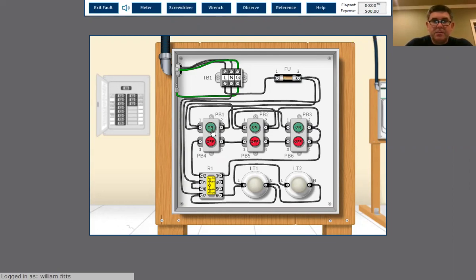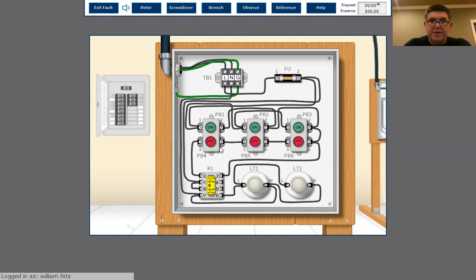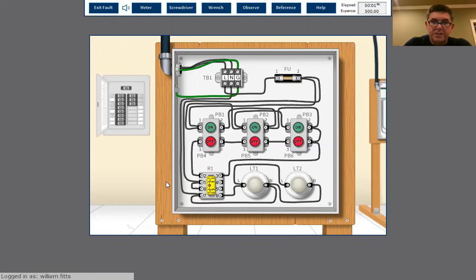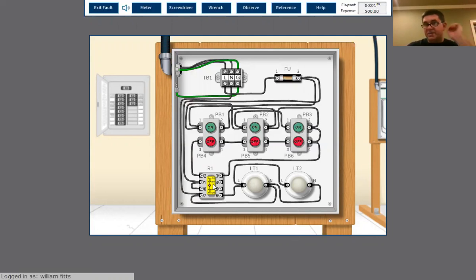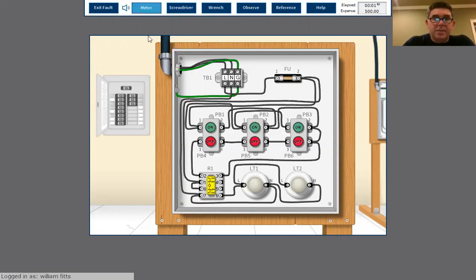There's no light, but what am I gonna look for? Right down here, see that relay? I'm gonna listen. In a control panel, a lot of times you can listen, but there may be a bad contact or whatever. The relay is turning on, which tells me I'm getting power all the way down to terminal 2. But from this point out, who knows? So I'm gonna focus in this area since I know my relay is turning on. Doesn't mean the relay is not bad - you can have a bad contact, so you got to keep that in mind.